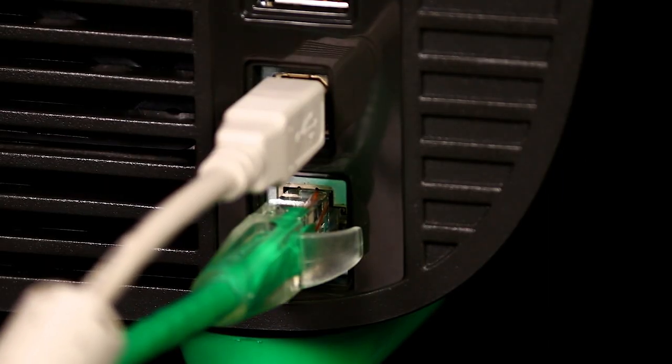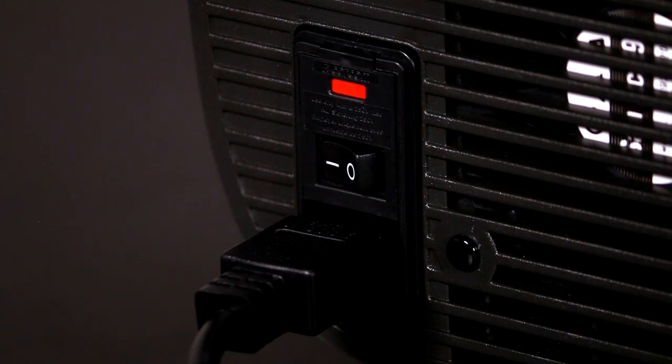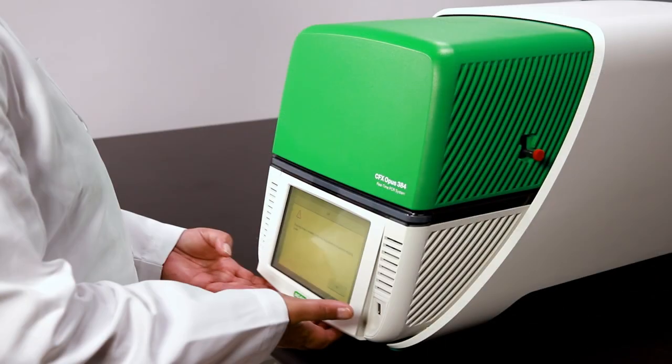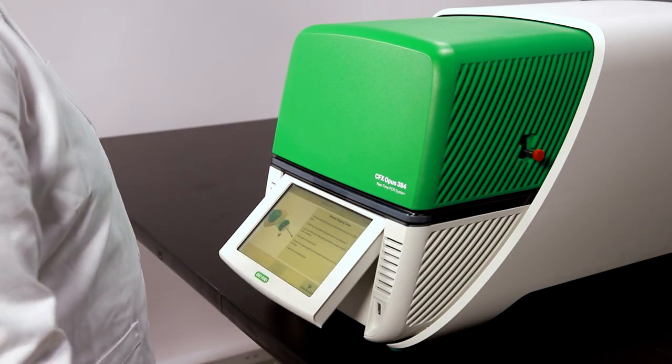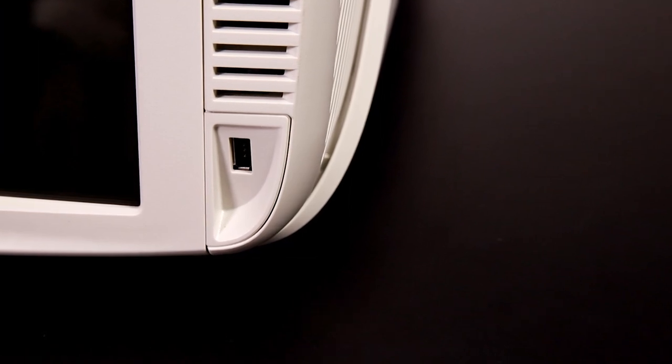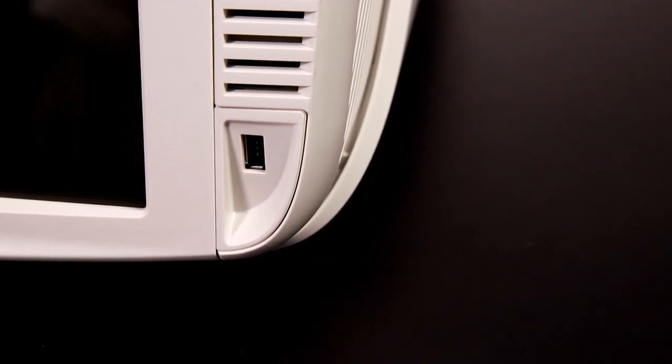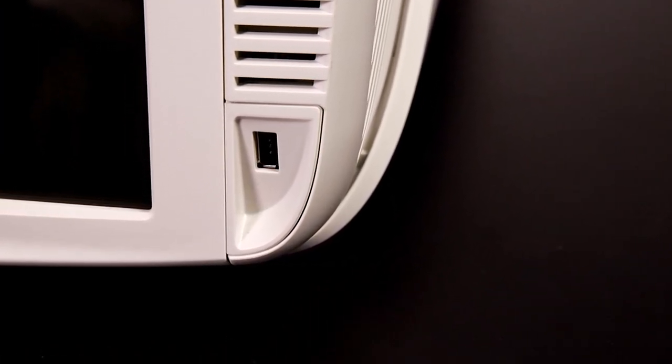You may also connect the Ethernet cable, USB cable, and optional Wi-Fi adapter if desired. Power on the instrument using the switch located at the rear on the left-hand side. Adjust the touch screen to a comfortable viewing angle. Note the USB port near the screen, which can be used to transfer data and protocols to and from a USB drive.